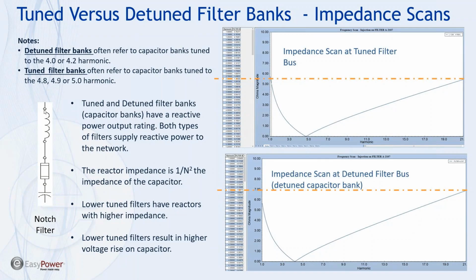And subsequently, it means that this reactor has to grow in size because we're supporting more voltage across the reactor. A fifth tuned filter would be 1/25th, right? 1 over 5 squared, 1/25th. The reactance would be a smaller value, and the 60 hertz current through it is the same, but yet we have a lower impedance, sorry, and therefore we have a lower voltage, so that reactor becomes smaller.